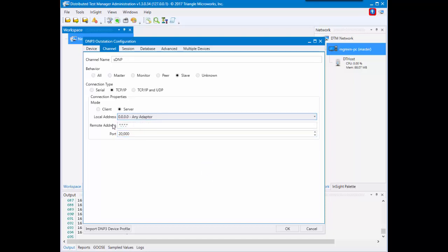The remote address is the address it's expecting to get communication from. Again, by default we leave it at its most generic star.star.star.star to allow it to connect to any device that is specifically looking for it. For DNP the outstation port is 20,000, so we'll leave it there, but if you'd like to play around with it you can change the port number as well.